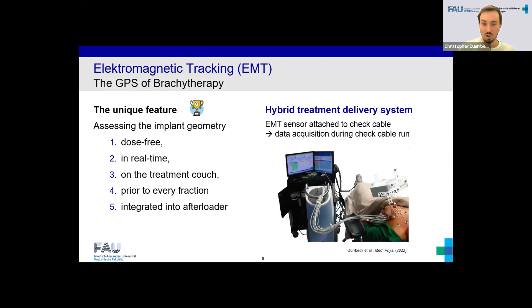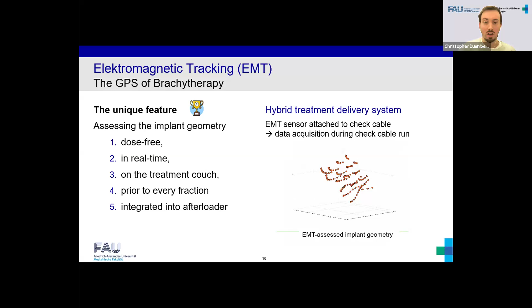And when we start a measurement, it looks like that. So this is an animation of actual data. And you can see this stop and go like motion of the sensor that is traveling through the catheters. These dwell positions, sensor dwell positions, not like source dwell positions, are spaced 1 centimeter apart. And like this, we try to cover the whole implant. Now, once this is done, we get a 3D representation of the catheter implant, just like we would with CT-based implant reconstruction for treatment planning.